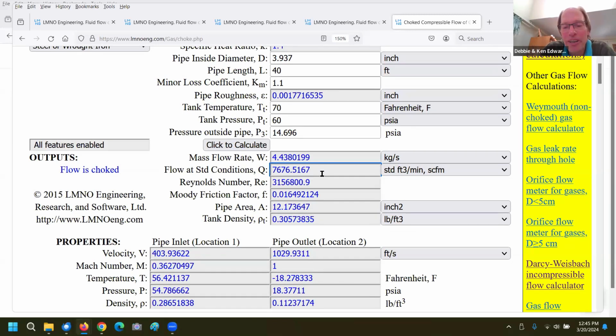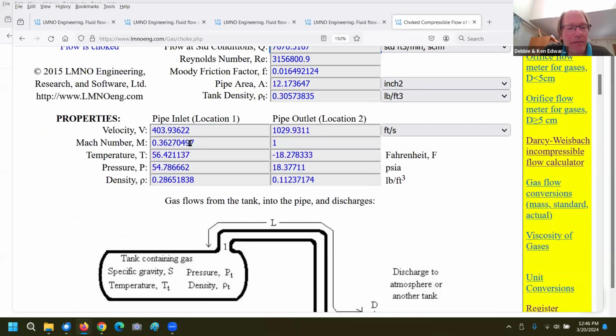In the international community, I believe it's called normal, meaning the same as standard here, maybe at a slightly different temperature and pressure, but normal cubic meter per second. So you know that's actually a mass flow rate because it's converted to a standard temperature and pressure. This will also give you the velocities and the Mach numbers at various points in the pipe system, and temperatures. You can have quite large temperature swings as you go through contractions and expansions.